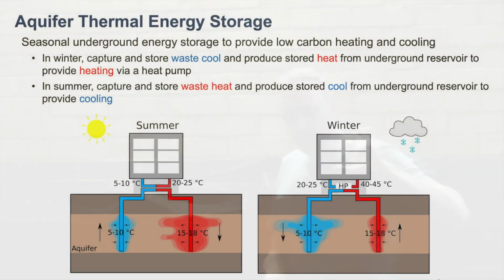So what we do in aquifer thermal energy storage: in winter, we're producing groundwater, passing it through our heat exchanger, using a heat pump to boost the temperature, and then we re-inject the waste cool water back into the aquifer. In the summer, we switch the wells around. So now, where we had been injecting, we now produce. We produce cooled groundwater, and often it's so cool that I don't need a heat pump anymore. I can just cool the building directly with that cooled groundwater, and then re-inject the waste heat back into the ground.